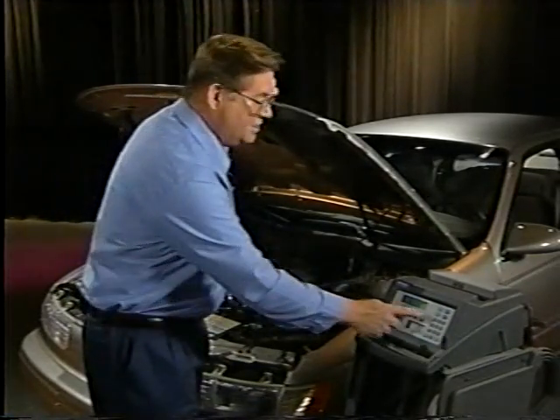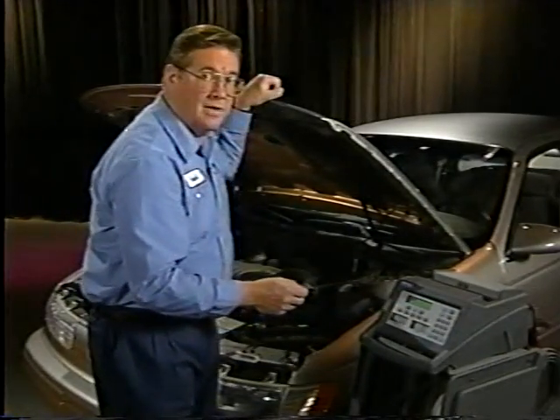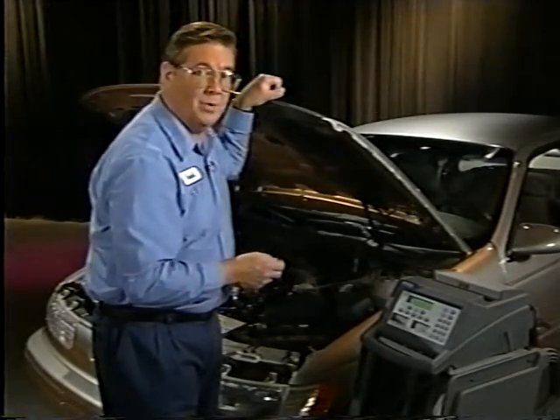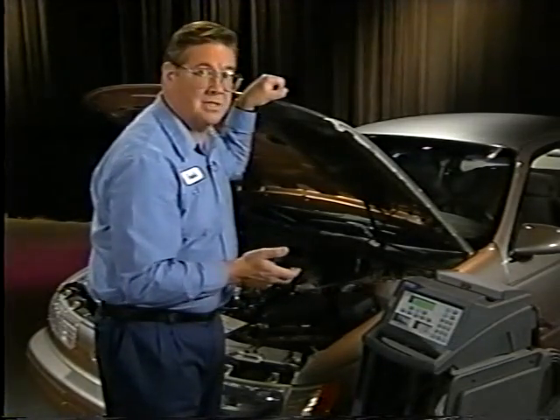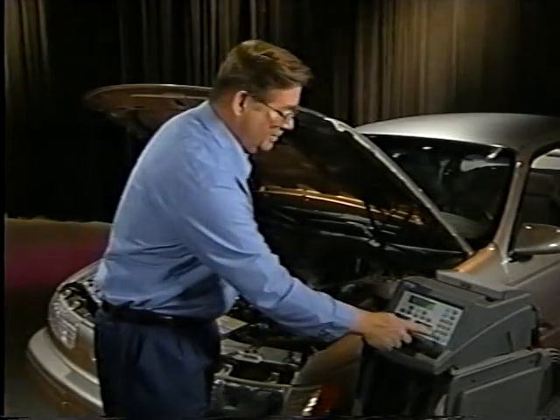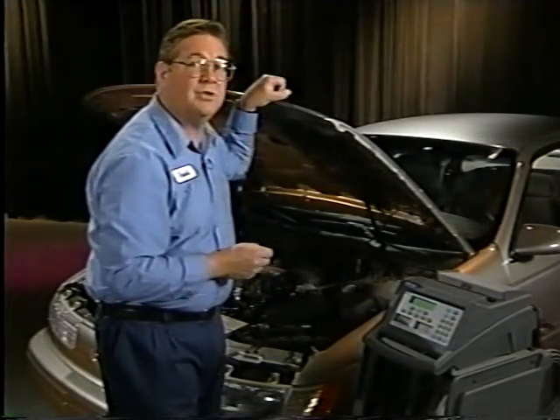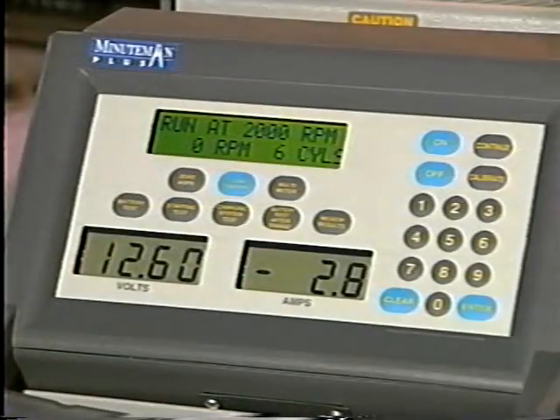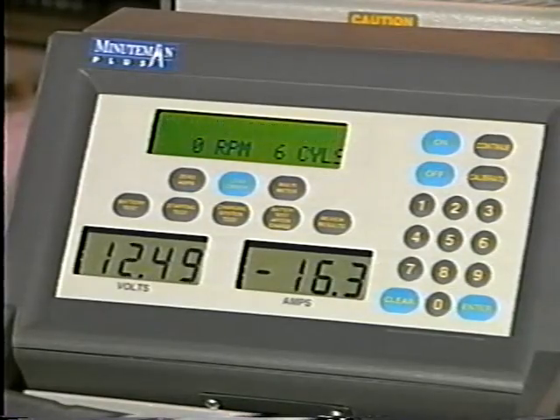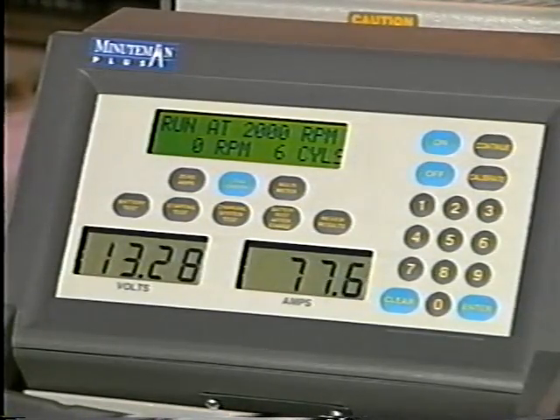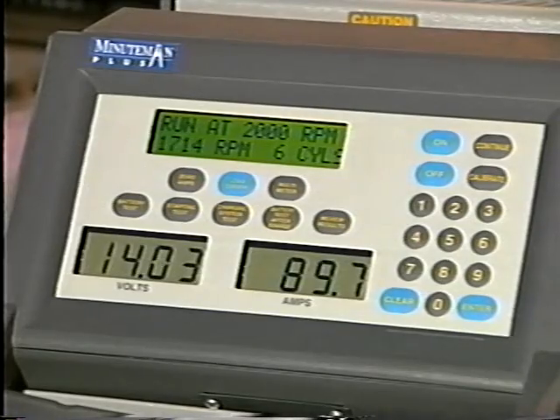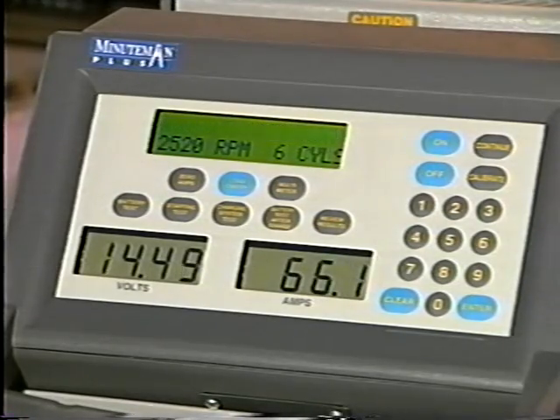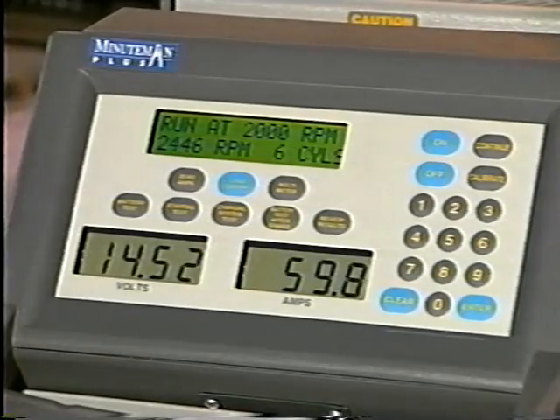You'll notice when you press a button, the Minuteman will sound a tone to verify the button was depressed. And if you ever make a mistake in entering data, there's a clear button you can press to re-enter the correct information. The liquid crystal displays are large and easy to read. The center display shows the messages and prompts generated by the microprocessor, including the status of the test being run. The LCD on the left will display the voltage at the battery load clamps, and the right display will show the amperage.